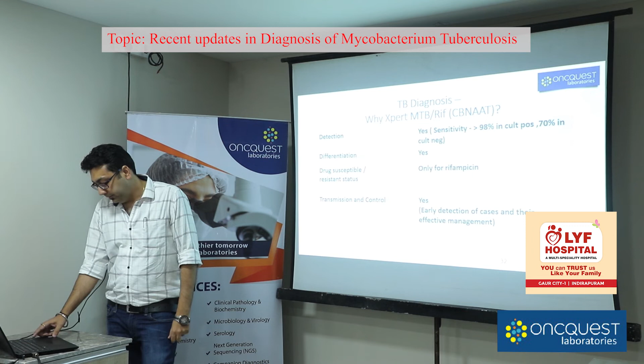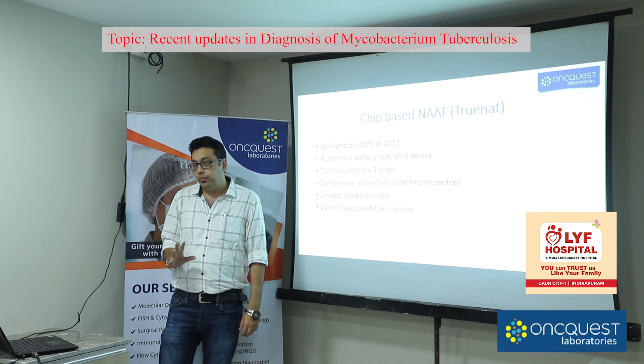There is another chip-based nucleic acid amplification technique by the name TrueNat, which was validated by ICMR in 2017. It is an automated, battery-operated device. The turnaround time is almost the same, 1 to 2 hours. It can be used at primary level health centers. Limited samples can be tested because in one device only one sample can be tested at a single time. It cannot speciate the MTB complex, so it can only tell you whether MTB is present or not. That's it.